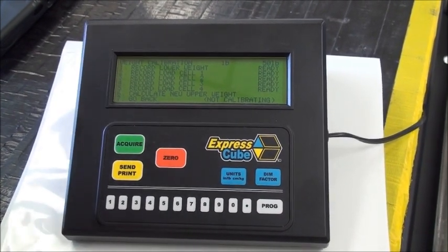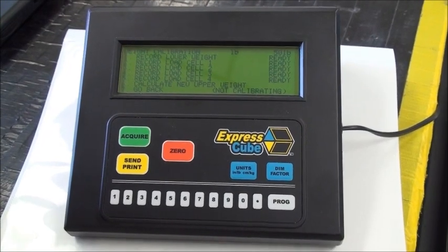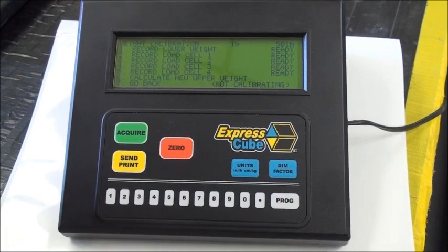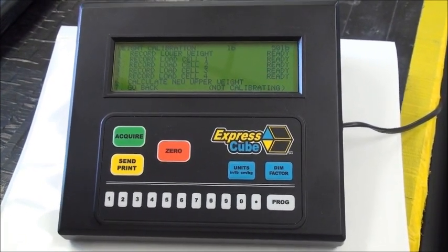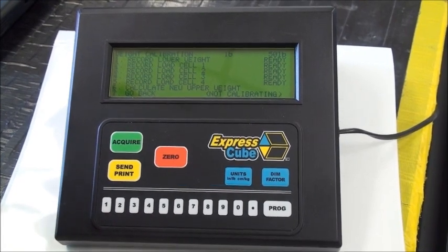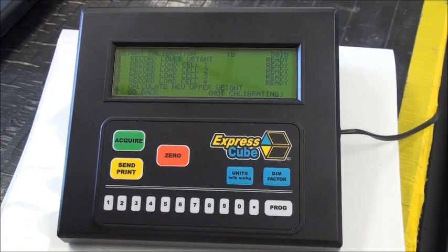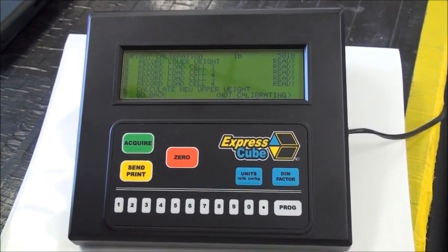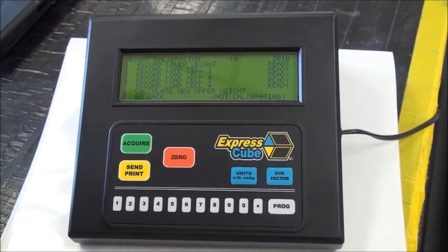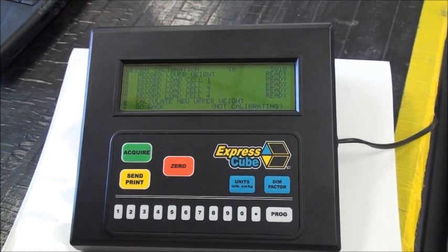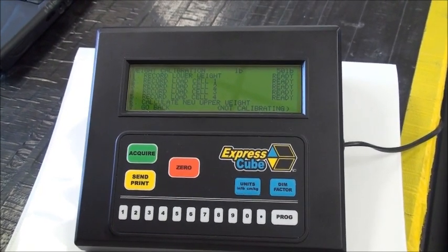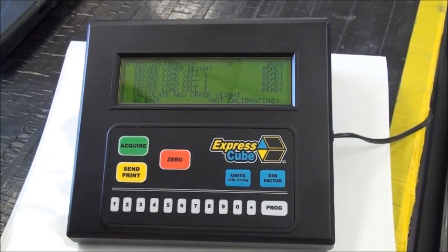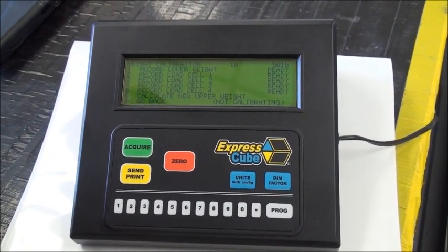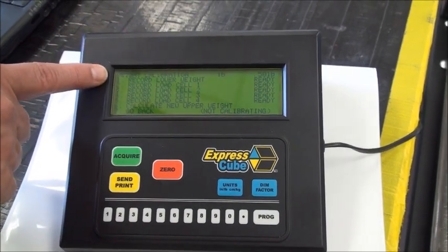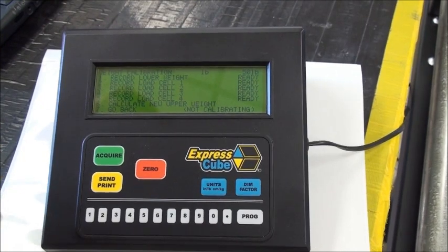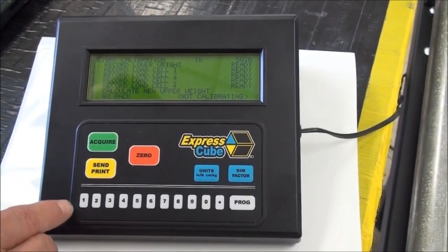In one of the areas when I was showing components, I showed the hub board and the fact that you've got 4 sensors that go into the board, and the board actually uses digitizing mathematics to find out the nuances of each of the 4 weights and to bring them in. So what we will be doing is 4 different measurements, and it's looking at all 4 load cells and seeing how they respond, and from that it can calculate any weight anywhere on the table to very good accuracy. First thing we do is to record the lower weight. What it basically says is the table is empty.